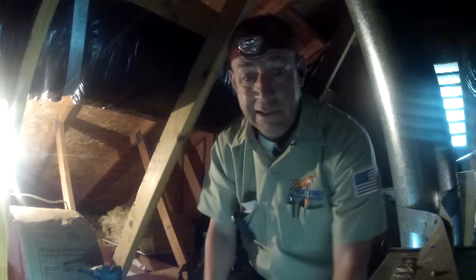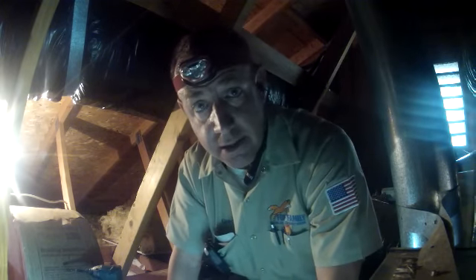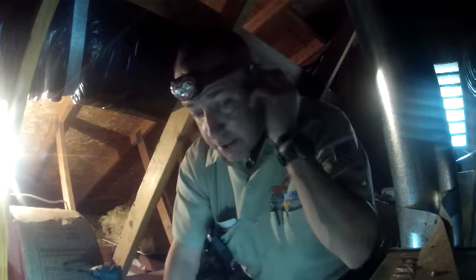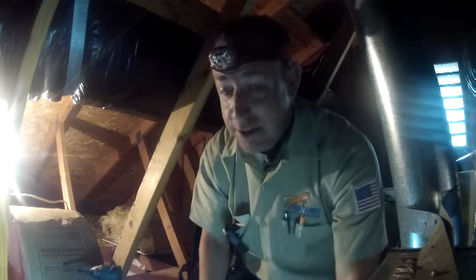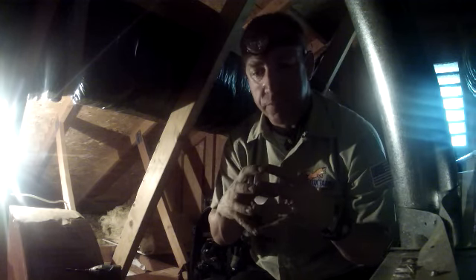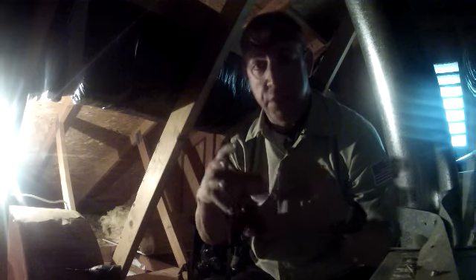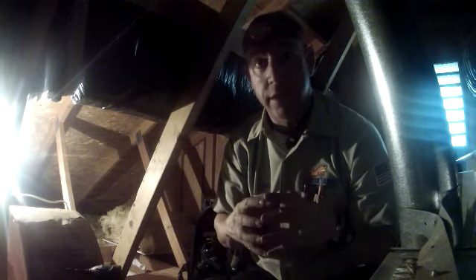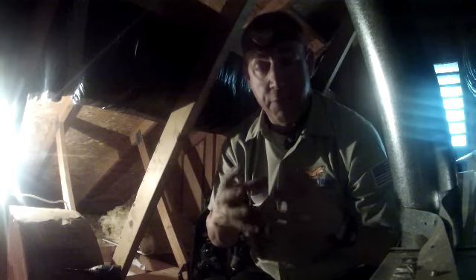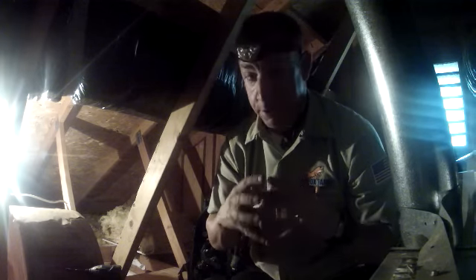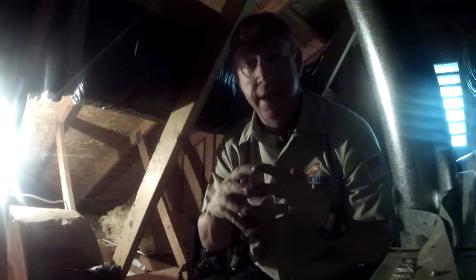And one of the first things to go on a bad heat exchanger is the eyelets start to crack. So I looked inside here and I didn't see anything. I don't even see really that much stress on that metal, because that metal expands and contracts over and over, 2,000 to 3,000 times every winter. And that's for years and years and years. This one's been doing it for 20 years. And that's why any system over 5 years old, 10 years old, you want to make sure you're looking at that heat exchanger to see if that metal has been expanding and contracting so much that cracking is starting to happen.